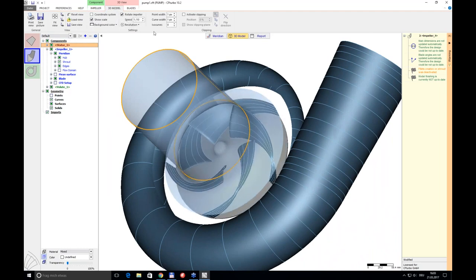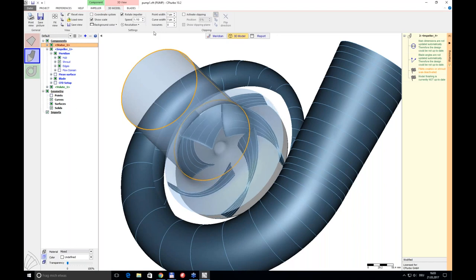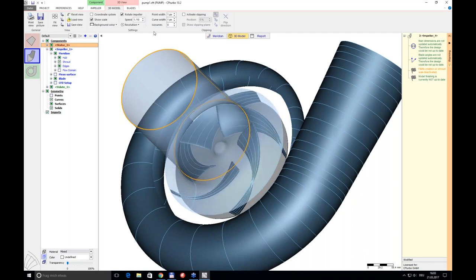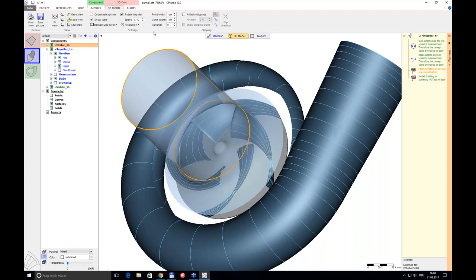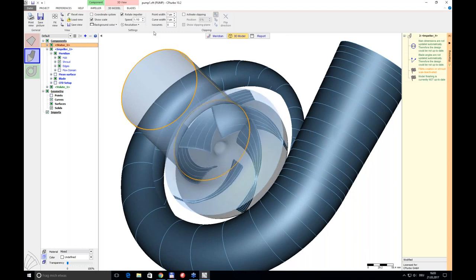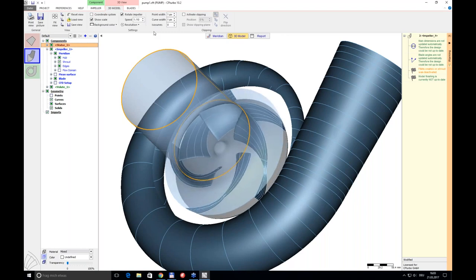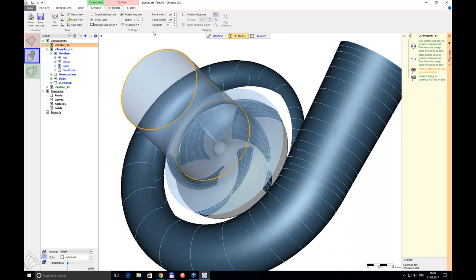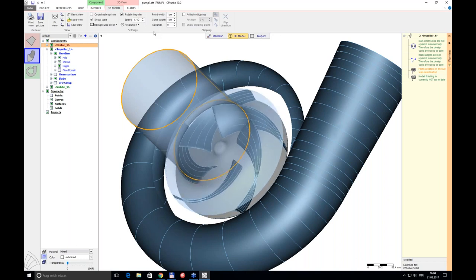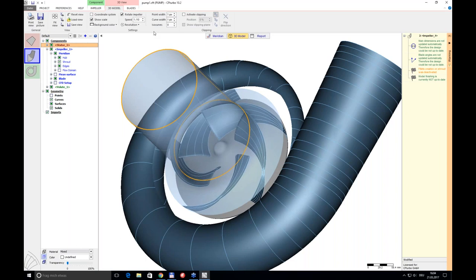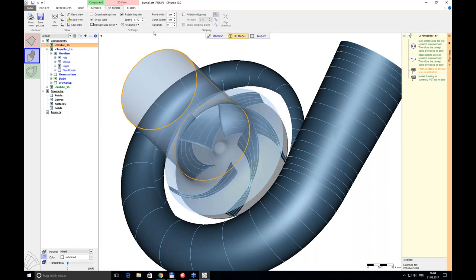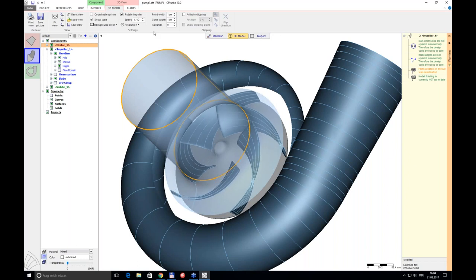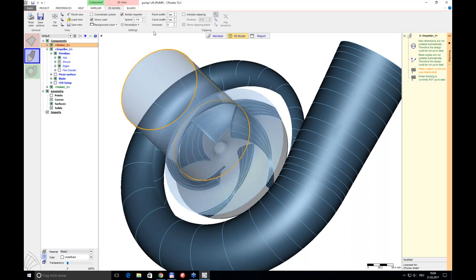Question: can we use standard NACA profiles in CF Turbo? That is possible to a certain extent. CF Turbo has a built-in profile manager with a couple of shipped NACA four-digit profiles, some of the 65-series, and point-based data. These can be incorporated in the blade profile design step. You can choose a profile from the profile manager, generate new ones, or import point-based data from Excel. For centrifugal modules, only the thickness distribution from the NACA profile is applied — the camber line is defined in a previous design step.